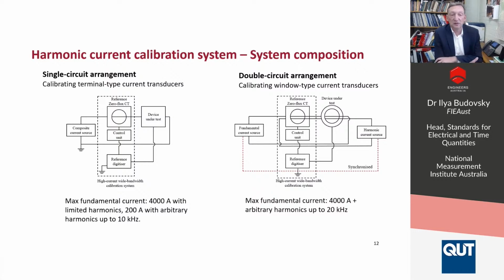This is ideal because we can calibrate terminal transducers. The problem is that no one, including us, can generate 4,000 amps with all required harmonics up to 10 kilohertz. We can generate 4,000 amps with a limited number of low order harmonics up to the 9th, or we can generate 200 amps with all required harmonics, and we can put more turns on the reference CT to build it up, but not to 4,000 amps.